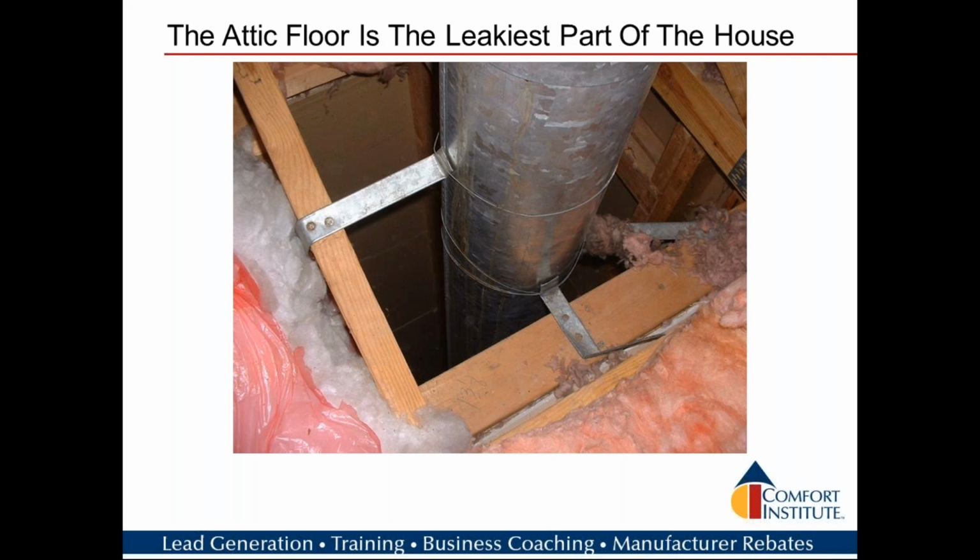One of the things, if you've ever done a load calculation, I've asked thousands of contractors about this as we talk in training classes. Where is the line in my load calc that says how much missing insulation and wide gaping open holes do I have in this attic floor? And the response is always the same, there isn't one. That's because it's assuming these are not there. When they are there, it's going to affect my heating and cooling system.